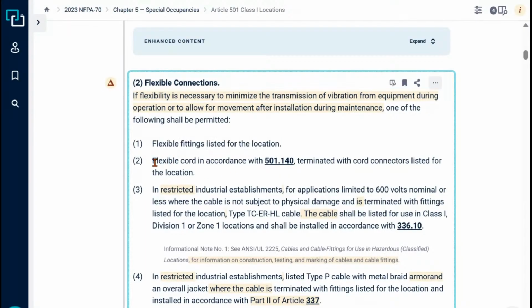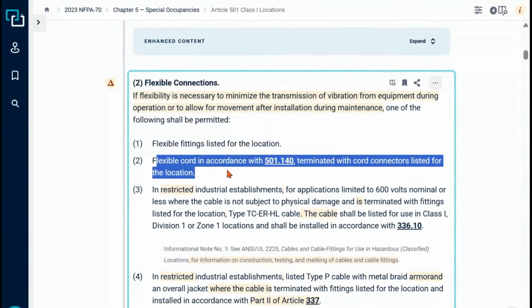It says flexible cords in accordance with 501.140, terminating with cord connectors listed for the location. So there is some limited applications for flexible cords in 501.140, very limited, but it also means that cord has to be terminated in a connector that is actually listed for that location. So it's going to be more like a sealing connector, and I'm sure those are pricey.